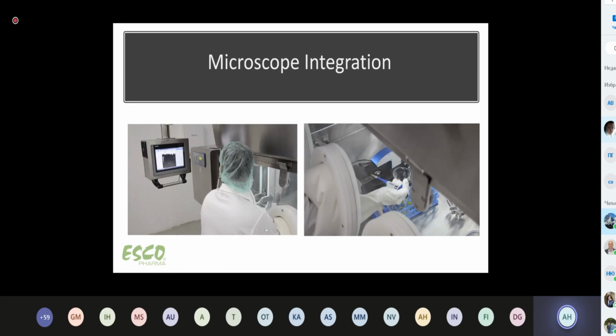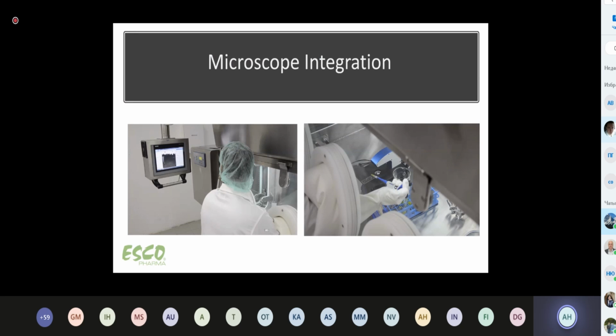Now, microscope. Obviously, in cell processing, we need to check from time to time whether the cells are growing well or not. But it's not possible to have a microscope and view the image in a conventional way. So the microscope must be integrated, and there must be a good guarantee that it is waterproof, IP rated, and most importantly, that it can withstand hydrogen peroxide, which can be quite corrosive.